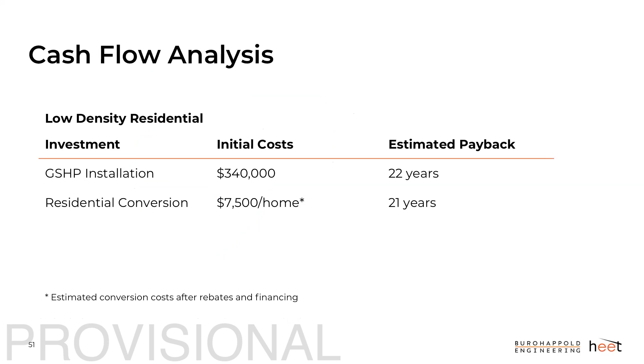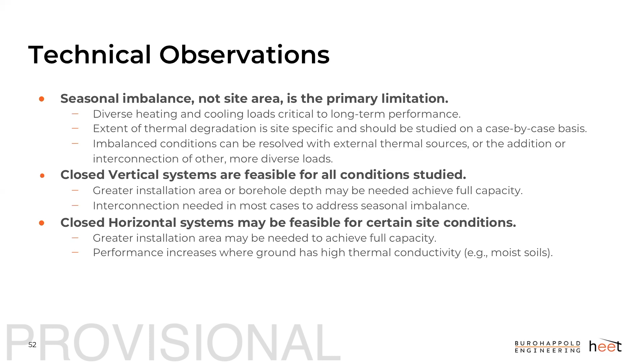So overall, and this is the summary, this seasonal imbalance is the main issue in terms of capacity. It's not the fact that you can't install enough boreholes, it's that you need to be able to mitigate this issue or else you face those ground condition issues. Like I said before, the closed vertical systems were the most feasible for all systems that we analyzed. And the closed horizontal systems could be used in certain conditions, but don't have the broad feasibility that the vertical systems have.